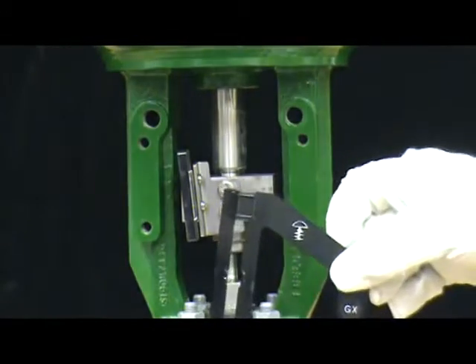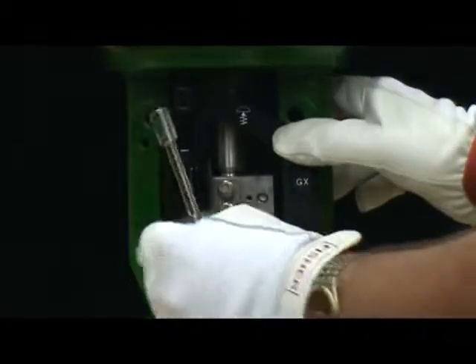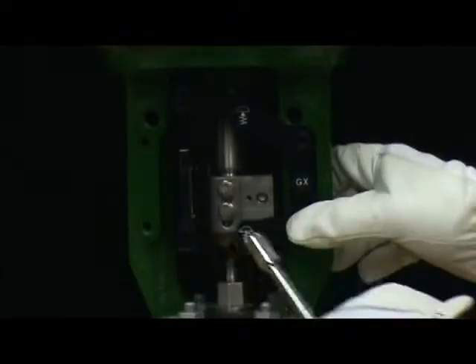Use the alignment template which came with the mounting kit. Attach it to the actuator yoke leg, and then adjust the array so we have the white line on the array above the white line on the alignment template.